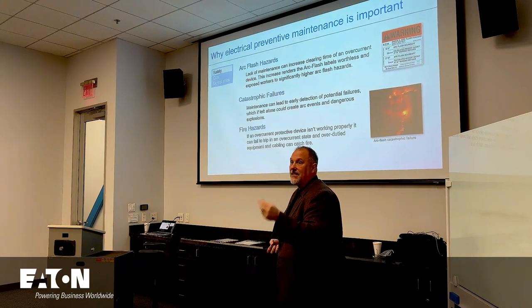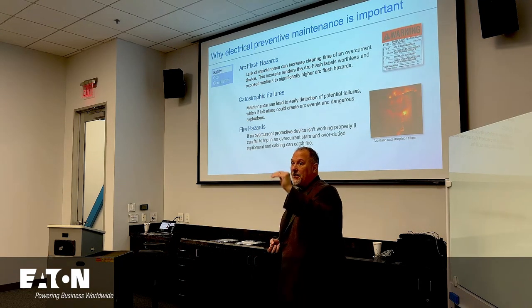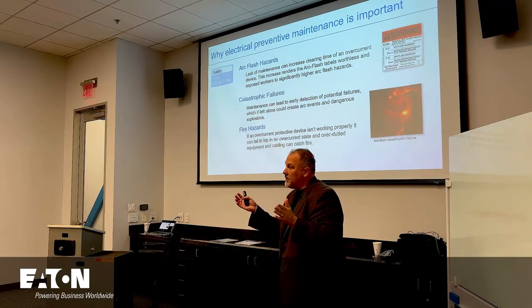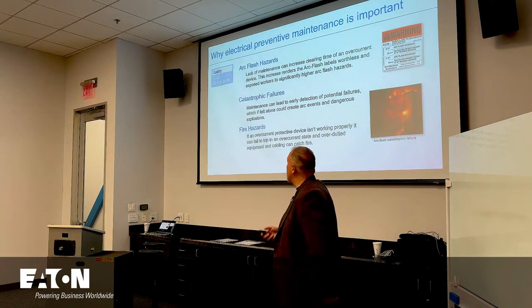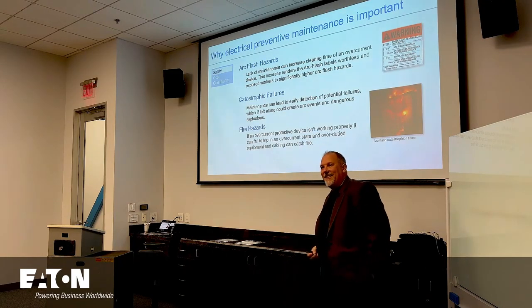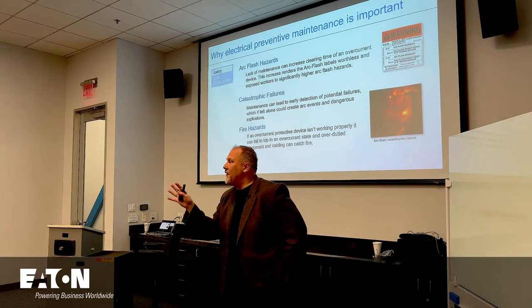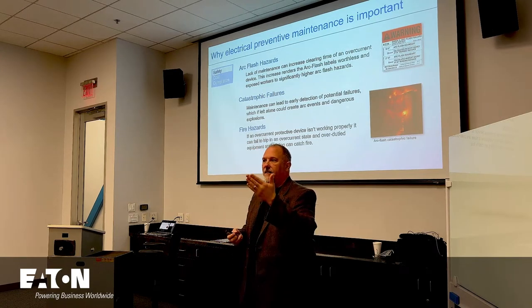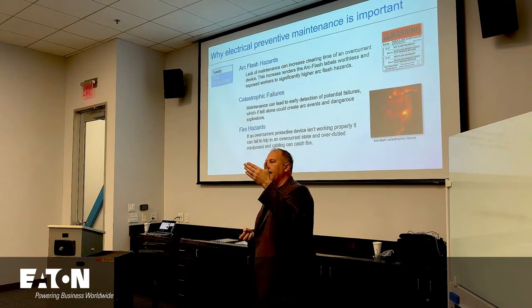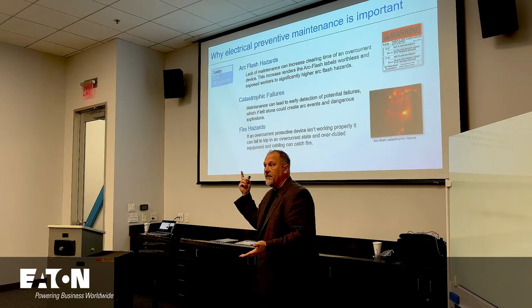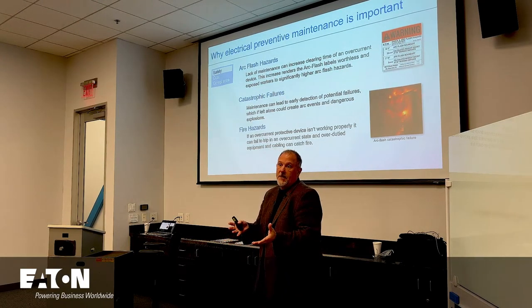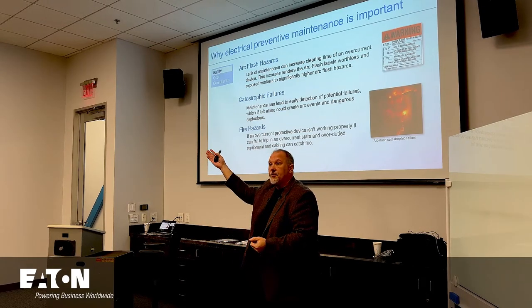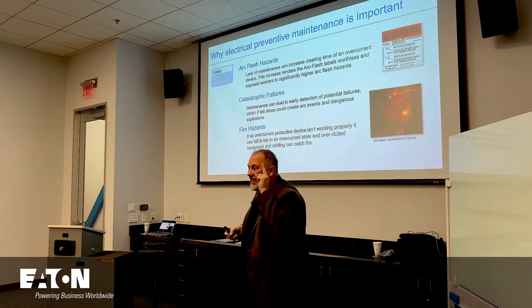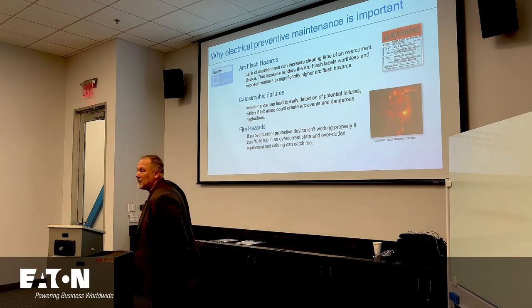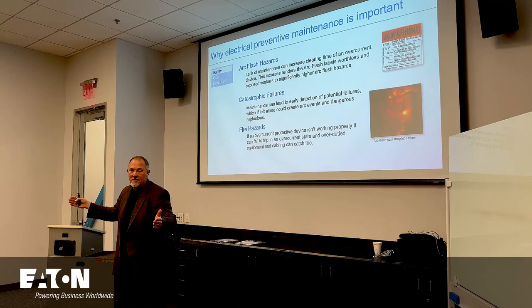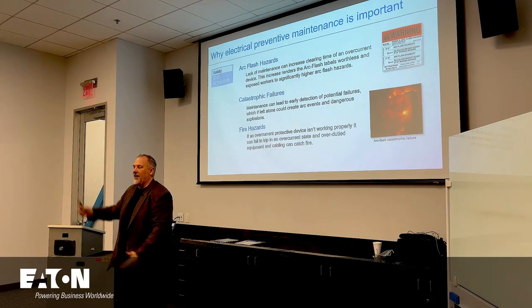When you think about the lack of maintenance, the likelihood of an event goes up, and quite possibly, depending upon the energy, the severity could go up as well. So with arc flash, likelihood and severity: if I'm not performing maintenance, I can increase the likelihood of an arc flash event, and the severity of that event is going to be dependent upon the clearing time of the upstream overcurrent protective device. And if I didn't maintain that upstream overcurrent protective device, what happens to the clearing time?